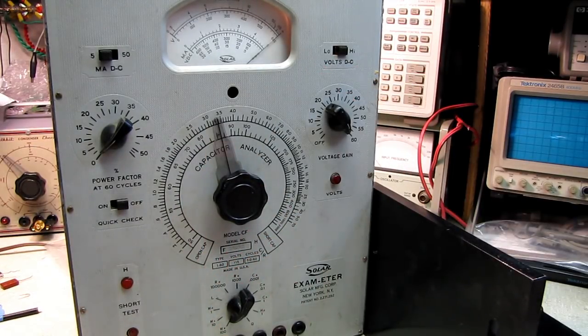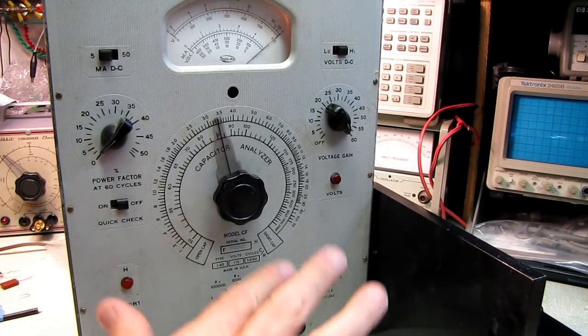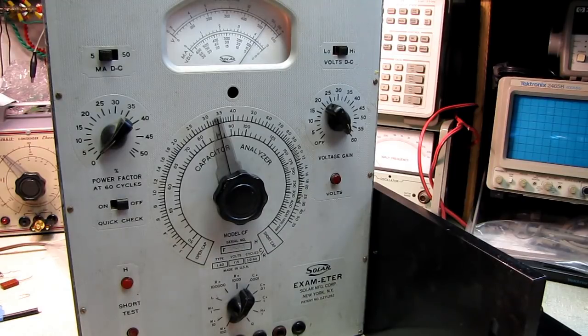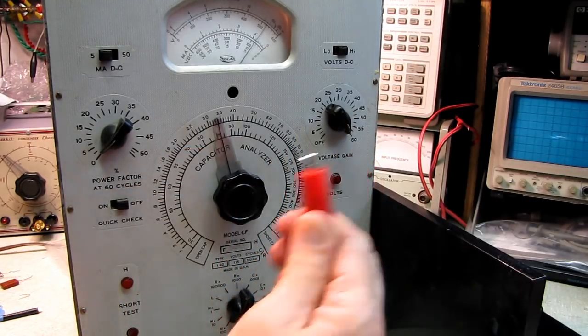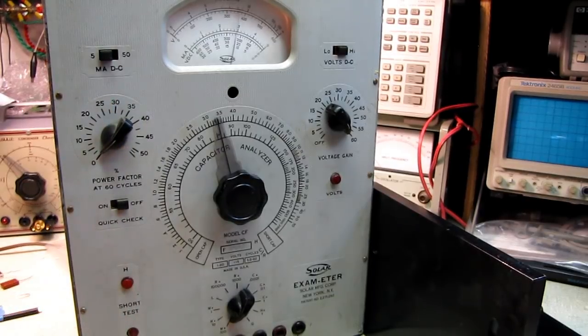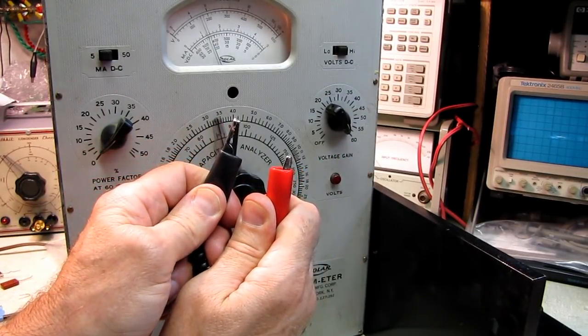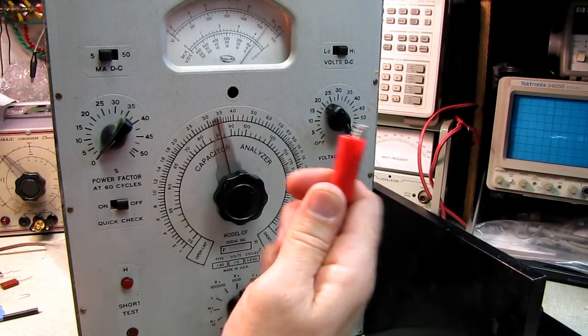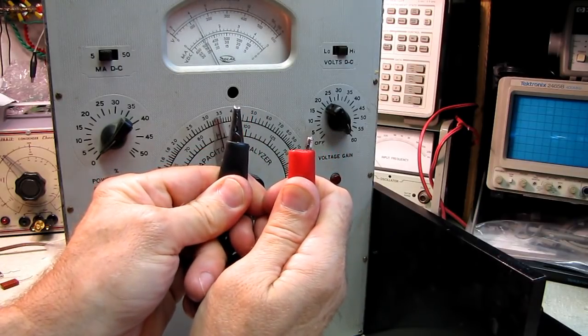Now, I'm going to try to do this without getting bit. We're going to plug in a couple of test leads here and see what we have. Right now we're on the 10 gigohm scale. I'm just going to put my hand on top of the test leads, and you can see it's showing leakage through the rubber insulation of the test leads. If I pick these up and just hold them, if I hold just one, that's the hot side, and that's probably noise on the VTVM, but obviously we're seeing leakage here. This is just noise pickup because I'm holding one lead. That's leakage. We're seeing right through the rubber insulation.